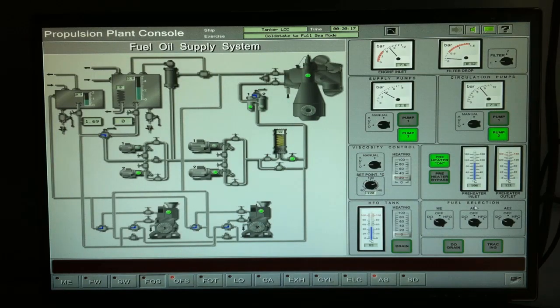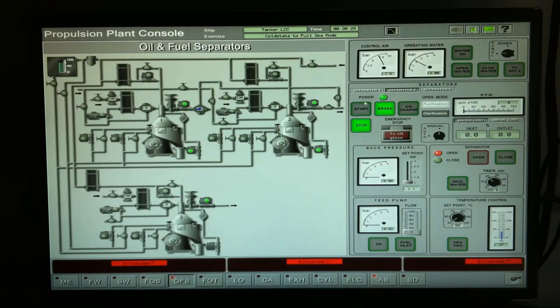Once we have achieved full ahead condition, set your fuel selection to heavy oil. Open your tracing steam, crack open your tank heating. Okay, let's run the purifiers. Open these valves for the operating water of the purifier. Fuel inlet to separator, open. Remove the brakes on all separators. Separator 1, start. Acknowledge alarm.